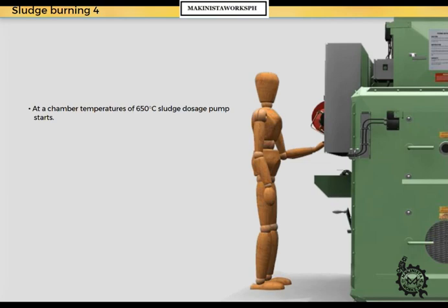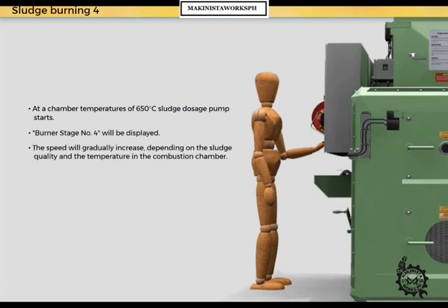At a chamber temperature of 650 degrees centigrade, the sludge dosage pump starts. Burner stage number four will be displayed. The speed will gradually increase depending on the sludge quality and the temperature in the combustion chamber.